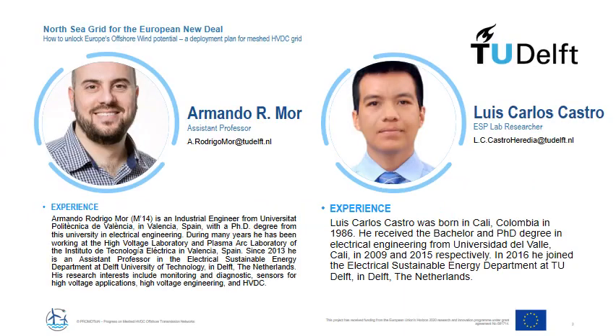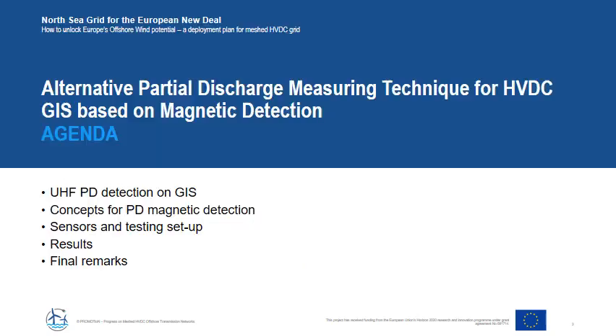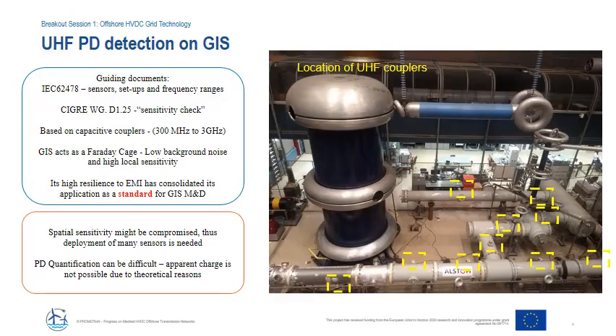Dear audience, on behalf of the High Voltage Laboratory of TU Delft, we want to take this opportunity to share with all of you the main results of an alternative partial discharge measuring technique for high voltage DC GIS based on magnetic detection. The measurements of partial discharges are used worldwide by manufacturers and utilities for the detection of defects as an important tool for the monitoring and diagnostics of high voltage GIS.